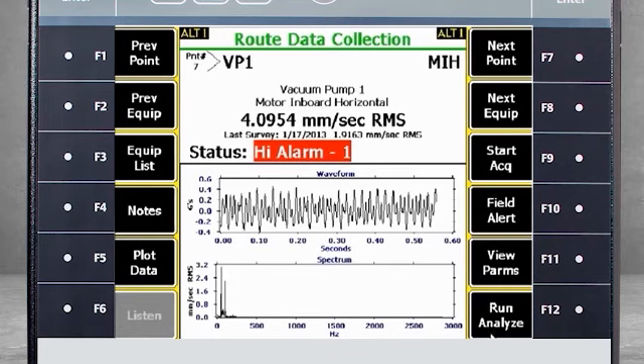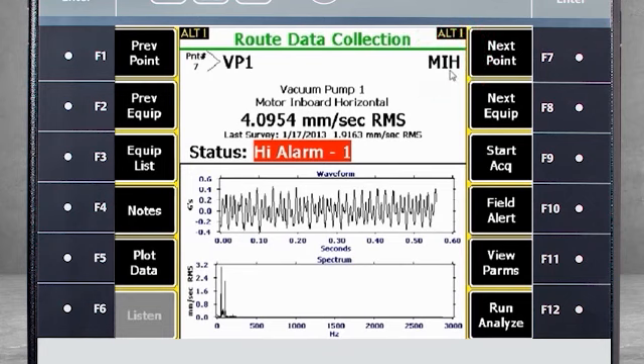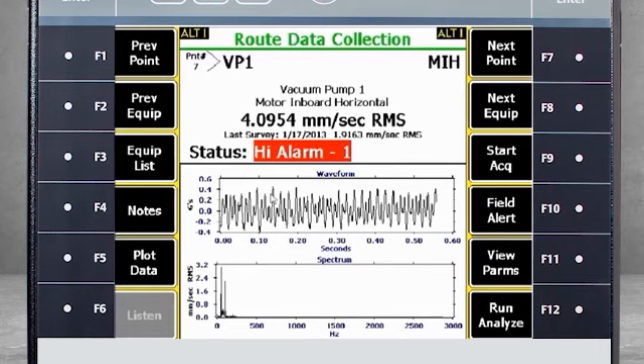In route mode, the first information you see is the point number. In this example, the point number is 7, meaning we are at point number 7 in this route. VP1 is the ID code of the machine, and here you can see the machine description. MIH is the ID code of the measurement point, and below the machine description you see the description of the measurement point — motor inboard horizontal. Here you see the overall value of the collected data, and below that the overall value of the previous measurement. Status tells you if an alarm level has been triggered. Below the status, you are looking at the waveform and spectrum of the collected data.